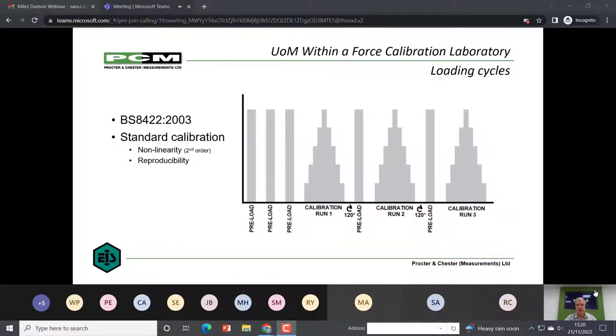If we look into 8422 in more detail, there are several calibration cycles described in this. The standard calibration is as seen here. If I just walk through what it is, you have a preload to full calibration force, hold for 60 seconds, and then drop back to zero, hold for 60 seconds. You repeat that three times. That gives you a kind of bedding in, exercising, three times run, so everything's ready for the calibration.